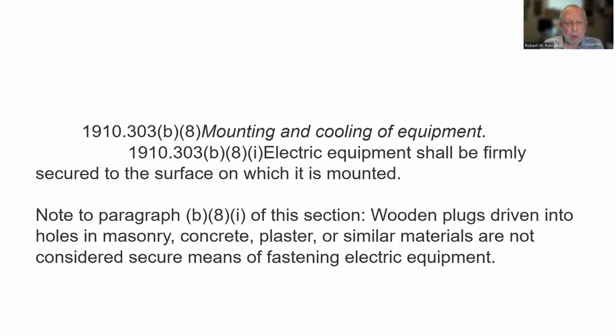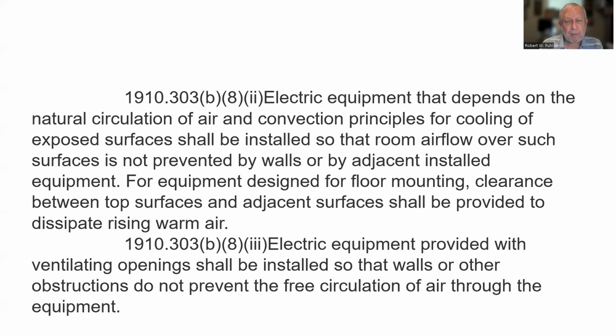Electrical equipment shall be firmly secured to the surface on which it is mounted. Wooden plugs driven into holes in masonry, concrete, plaster, or similar material are not considered secure means of fastening electric equipment. Notice they said wooden plugs. Rawl plugs are not wooden. Rawl plugs are designed for that surface, and they're probably okay. Rawl plugs are those plastic ones. They're different colors for different sizes. And those are pretty sturdy.